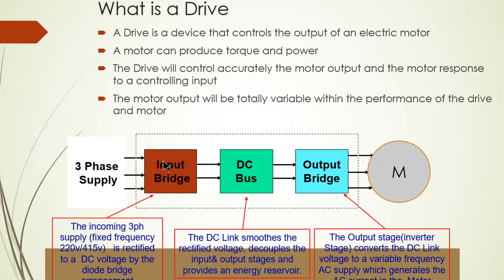The incoming voltage — 220 volts or 415 volts — is rectified to a DC voltage by the diode bridge. So when the power is incoming, that means 220V or three-phase, it goes through the input bridge section. The input bridge converts the three-phase AC voltage to DC. The DC bus section then removes all spikes from the DC voltage.